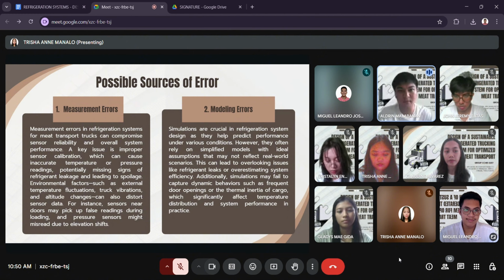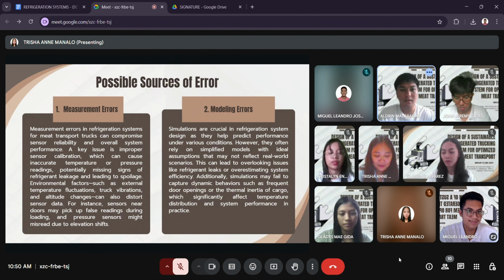Now proceed to possible sources of errors. Number one is measurement errors. Measurement errors in refrigeration systems for meat transport trucks can compromise sensor reliability and overall system performance. A key issue is improper sensor calibration, which can cause inaccurate temperature or pressure readings, potentially missing signs of refrigerant leakage and leading to spoilage. Environmental factors such as external temperature fluctuations, truck vibrations, and altitude changes can also distort sensor data. For instance, sensors near doors may pick up false readings during loading, and pressure sensors might misread due to elevation shifts. Number two is modeling errors.